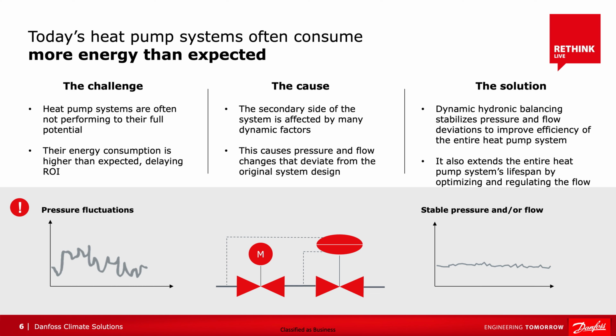And what that also does is it's going to improve our reliability. It's going to extend the heat pump system's lifespan and optimize the flow. Hydronic balancing, we found, is essentially required for complete system efficiency. It is the key to establishing proper indoor comfort while maintaining energy efficient system operation in all climates and the entire year.